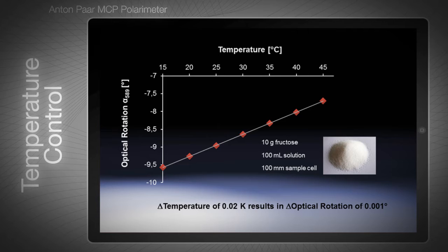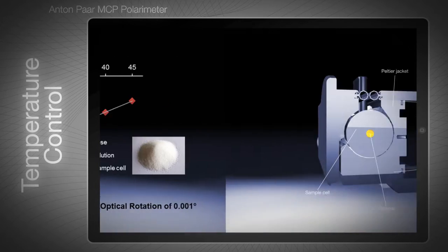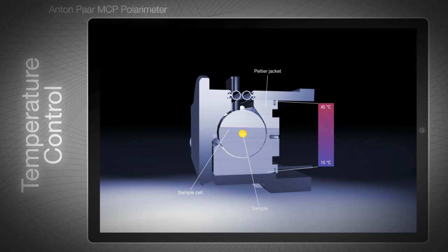Excellent temperature control is important for the majority of samples. This is a cross-section of the MCP sample cell located in the metal Peltier jacket. The Peltier jacket is heated or cooled quickly by powerful Peltier elements, significantly reducing your waiting time.